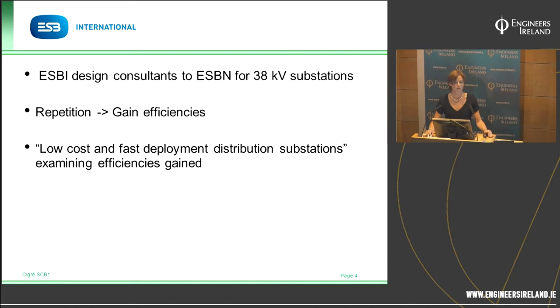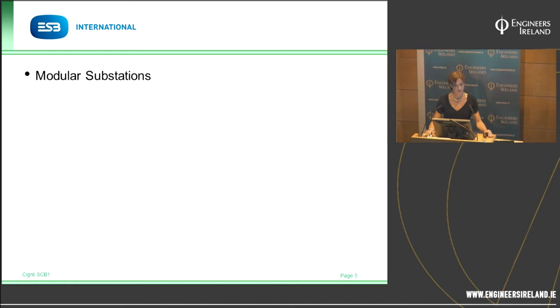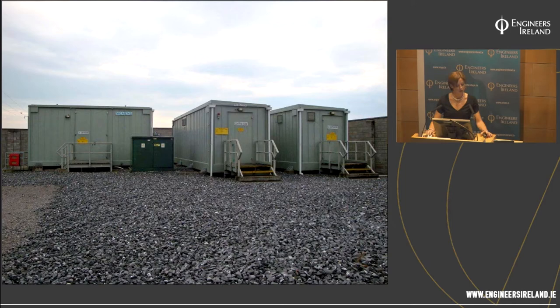The biggest efficiency was around the use of modular substations. Now, previously, during that pilot of 11 stations, we were replacing outdoor AIS stations with indoor GIS stations. So a large conventional blockwork building was built, and into it was put the 38 and MV GIS and the associated control and protection and battery systems. In modules, the 38 kV is fitted into one module. That's the 38 kV module there. That's the MV module with the MV GIS inside, and that's the control and protection module at the end.